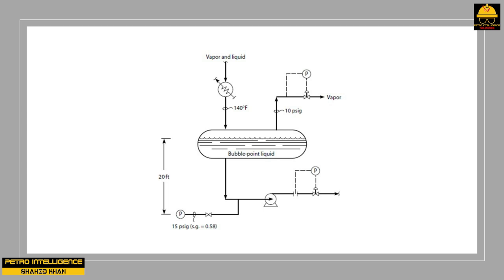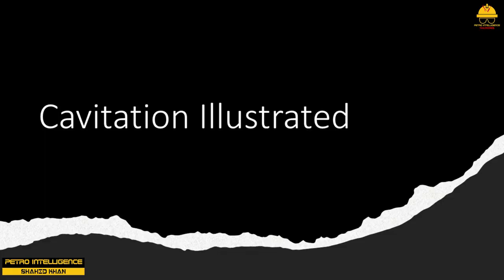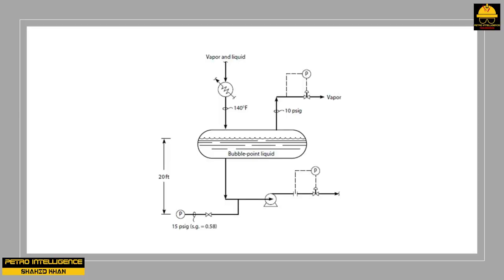When the required NPSH of a pump equals the NPSH available to the pump, the pump will cavitate or slip. To illustrate: the liquid in the vessel is presumed to be in equilibrium with the vapor leaving the drum, meaning the liquid is at its bubble point pressure and the vapor is at its dew point temperature. The vapor pressure of the liquid is 24.7 PSIA — 10 PSIG plus 14.7 PSIA of atmospheric pressure.